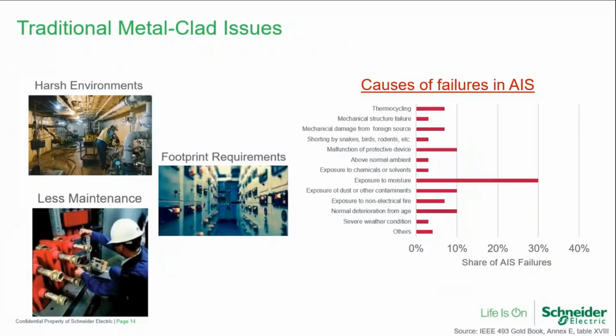So we've talked about a lot of benefits of GIS and SIS compared to traditional styles of switchgear, but I think this is one of the biggest ones, when you look at the IEEE 493 Gold Book. It's basically a utility study done to analyze what were the most common causes of failure with metal-clad switchgear. And so I'm putting this into the common causes of AIS switchgear. There are a lot of big ones on here. Exposure to moisture is very high up there. Deterioration due to age, exposure to dust and other contaminants, malfunction of the protection device, thermocycling, basically the heat and cold cycle that it experiences. These are all large contributors.